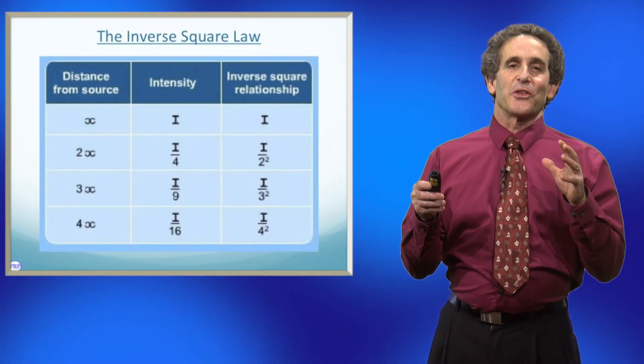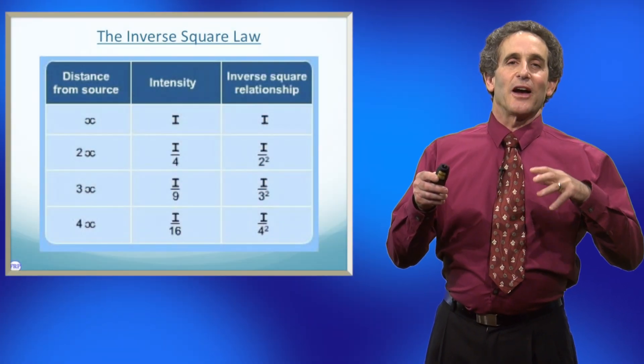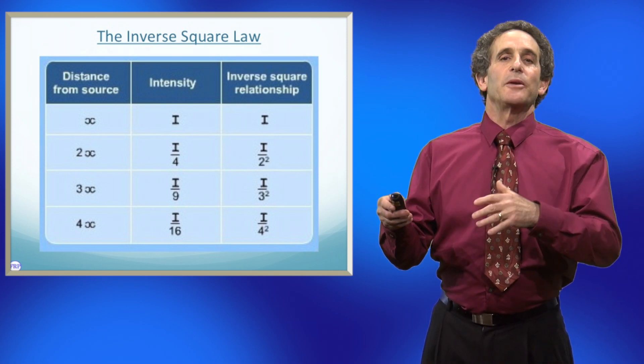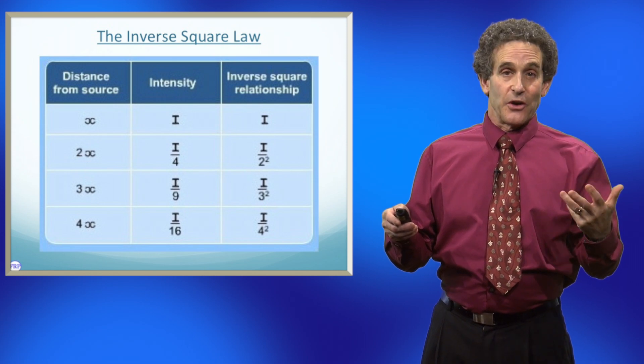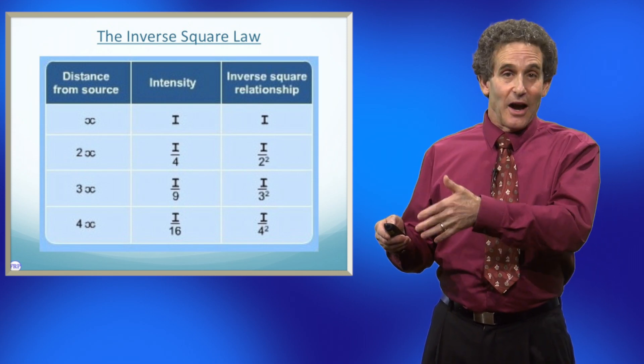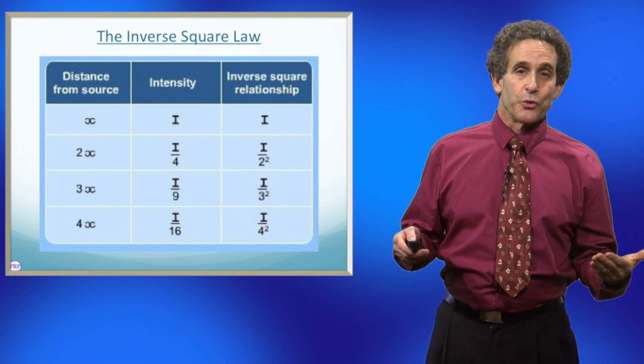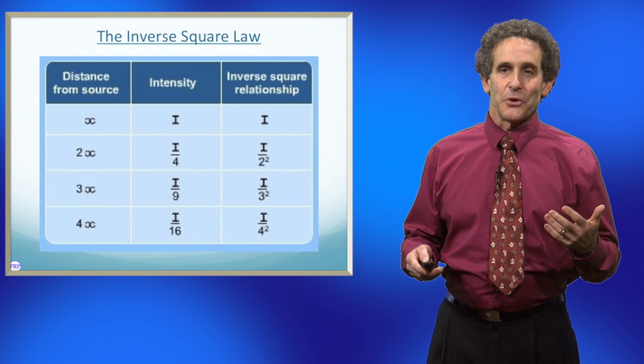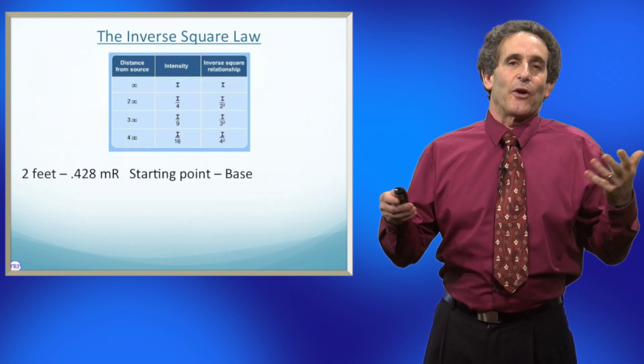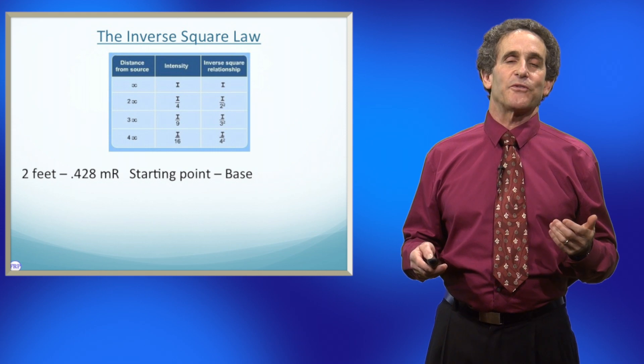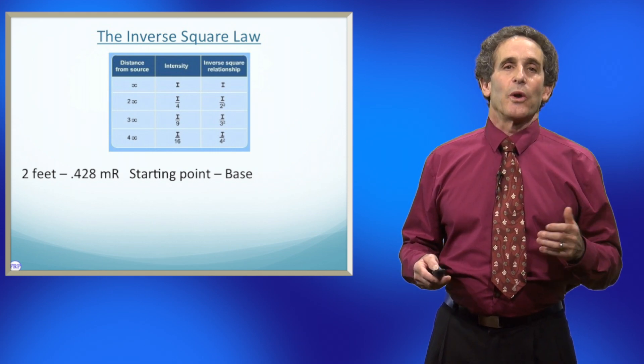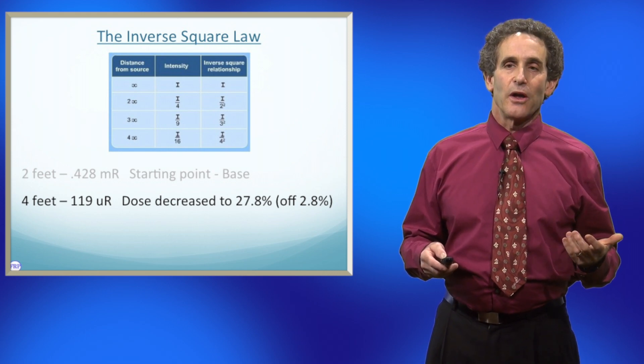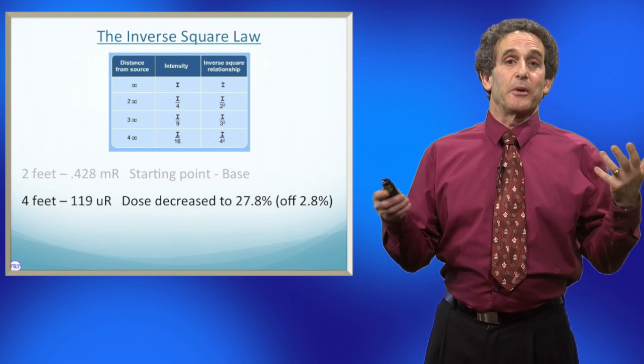We wanted to show you this chart to go over how it all works. When you double the distance, you're going to be at one fourth of the dose. When you triple the distance, it's going to be one ninth. And when you quadruple it, you're going to be one sixteenth. Here are the numbers we had in the room. At two feet — our starting point or base — it was 0.428 MR. When we doubled that to four feet, it dropped down to 119 micro R, which should have been a quarter.